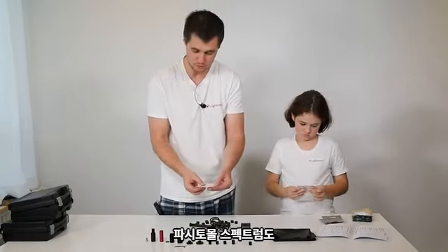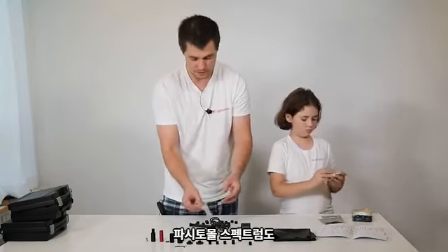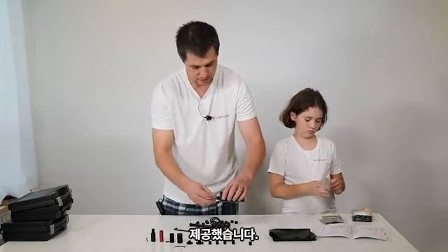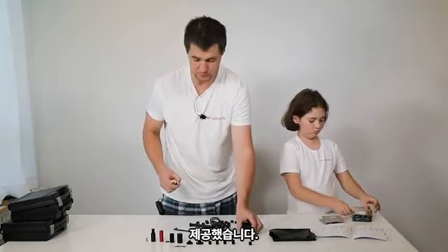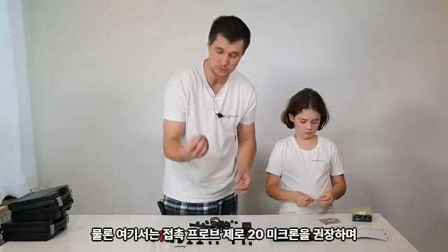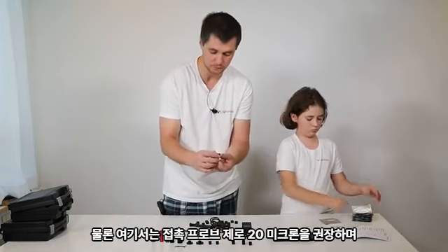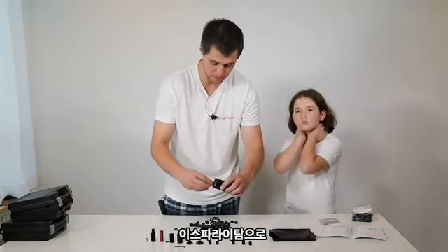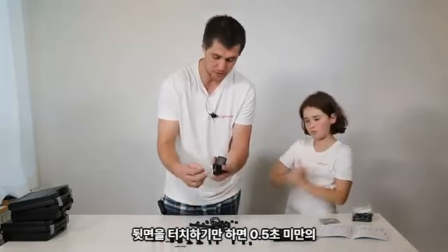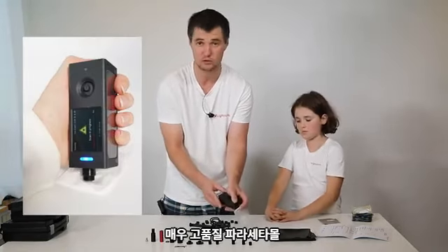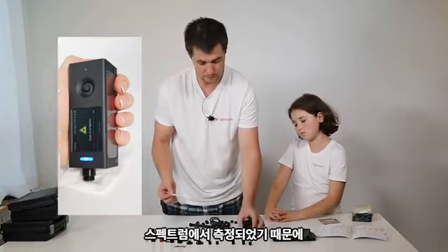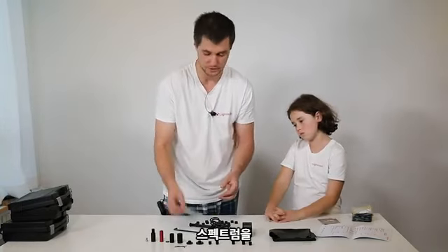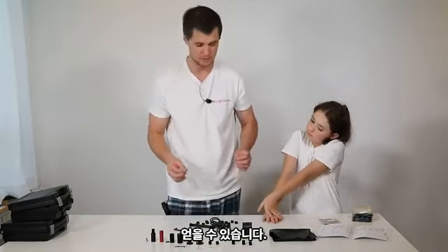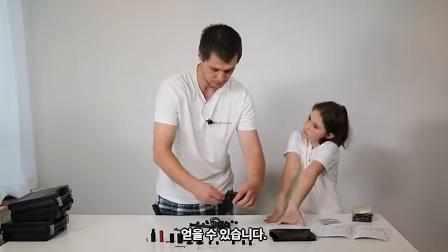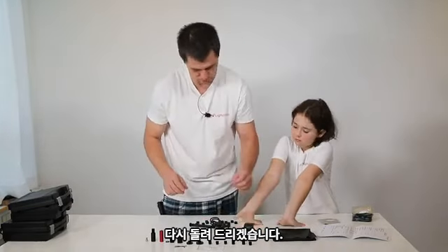And the last box was paracetamol. Paracetamol in a bag, and we also provide the spectrum of paracetamol measured. And here, of course, we recommend the contact probe 0.20 microns, and you just touch the bag with paracetamol and you should get a spectrum as it was measured in the factory. Very high quality spectrum of paracetamol in less than half a second. Let me put the contact probe back here.